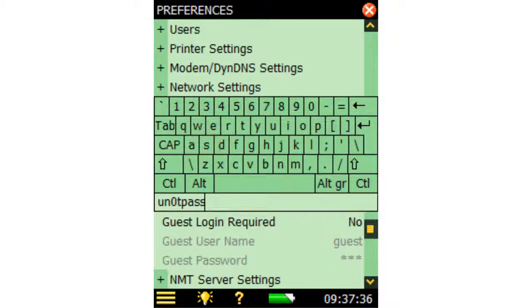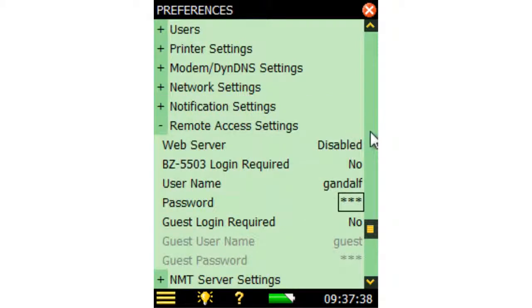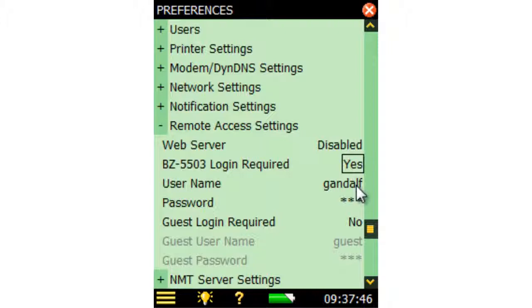By setting the BZ5503 login required option to Yes, password protection will then also prevent unauthorised access when connecting to the instrument for Measurement Partner BZ5503.